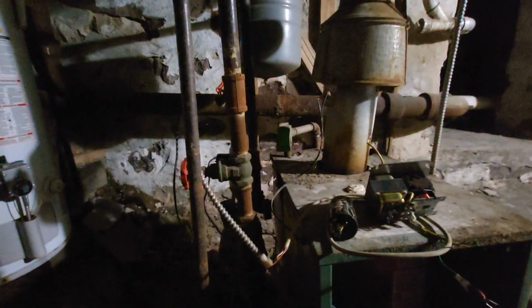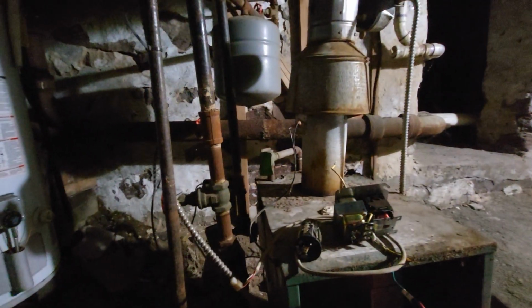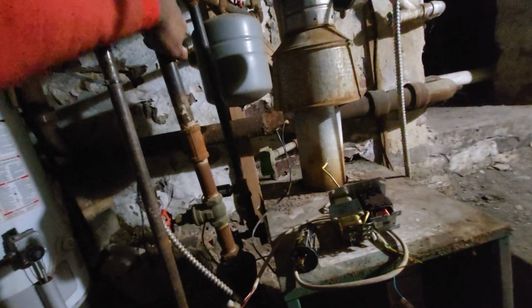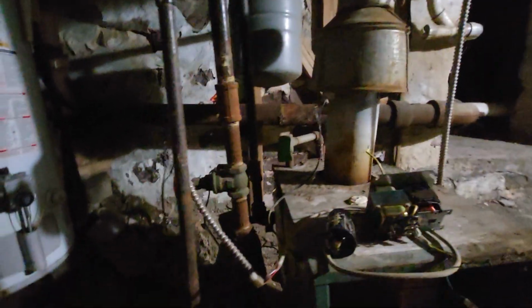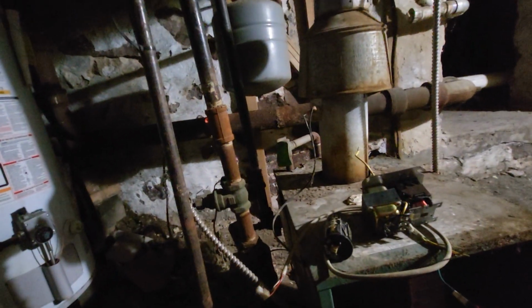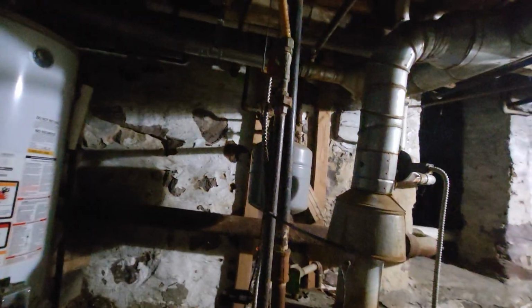Guys, I'm gonna clean up a little bit. I gotta take some trash outside. I'll be right back. Guys, my return pipe is starting to heat up. What I'm gonna do is, I think we might be good here. I'm gonna put all my stuff back on the truck. I'm gonna get my infrared thermometer, and I'm gonna check all the radiators on the second floor. Worst case, if all my pipes are hot down here and the radiators are cold, I'm just gonna bleed the air and then come down here, refill it, and check again. But I think for the most part, everything's rocking and rolling. Worst case, if I gotta bleed air, so be it. But if everything's hot, then we're good to go.